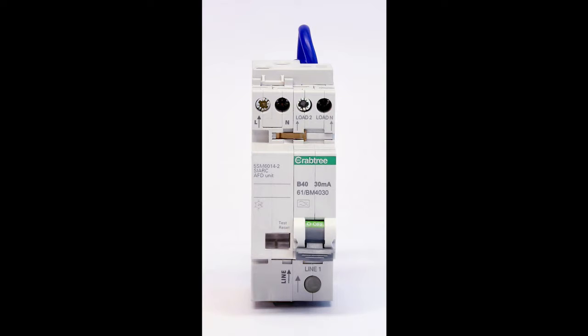30 mA RCD protection extended. Today's typical domestic installation will have 30 mA RCD protection on every circuit, especially as another new regulation in the 18th edition, Regulation 411.3.4, has extended the use of 30 mA RCDs to include all lighting circuits in dwellings, all of which means that each circuit in a consumer unit needs to have several types of protection against a variety of potential faults.